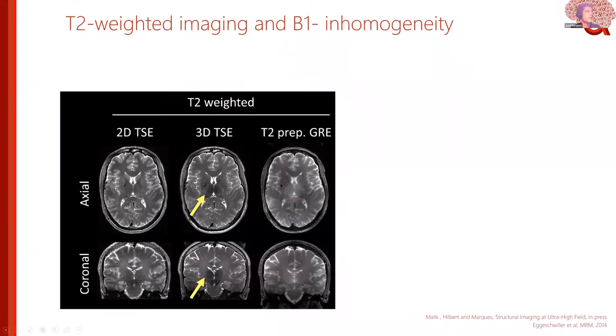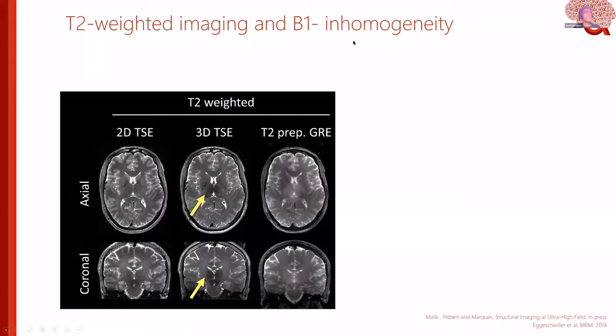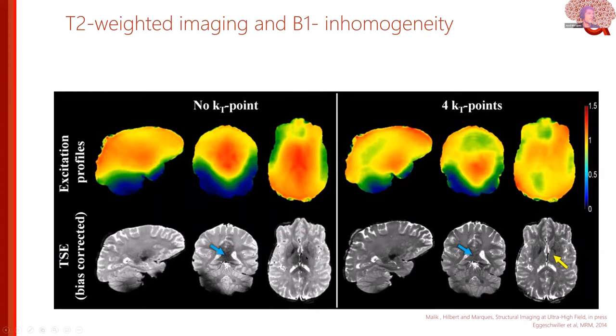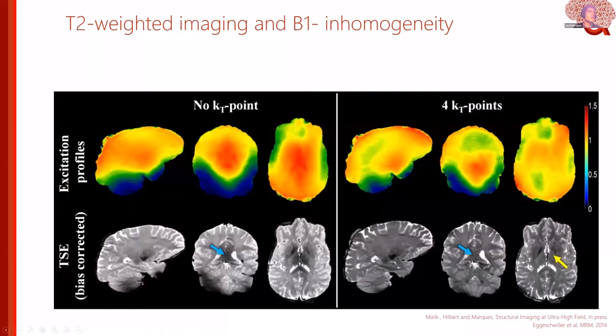The third type of imaging important to discuss is T2-weighted imaging — the one most sensitive to B1 inhomogeneity. These are three flavors of T2-weighted imaging, and thalamic structure is often claimed to be visible here. Interestingly, when we acquired T2-weighted images with apparently nice thalamic structure and then corrected the B1 inhomogeneity using adiabatic pulses to homogenize the flip angle in the thalamic region, the thalamic structure disappeared entirely. So it is quite tricky to interpret T2-weighted thalamic contrast at 7T.